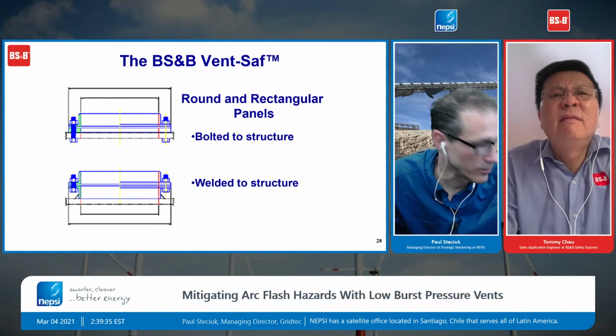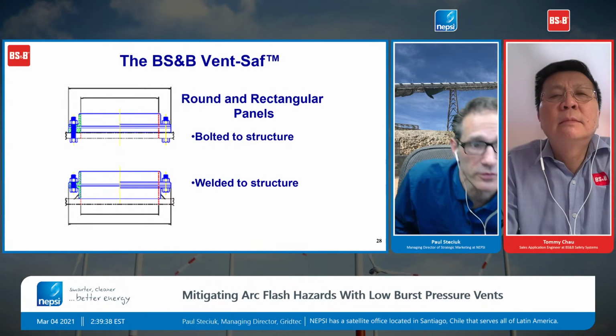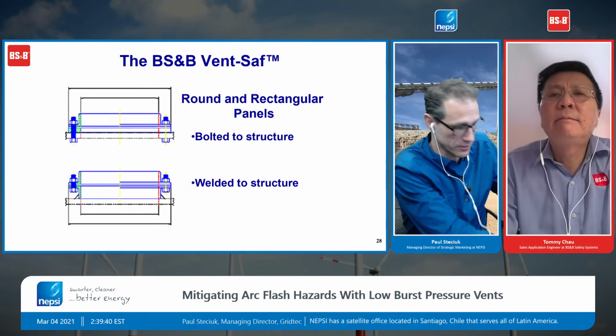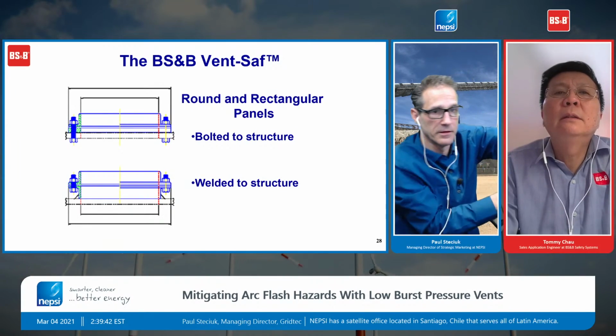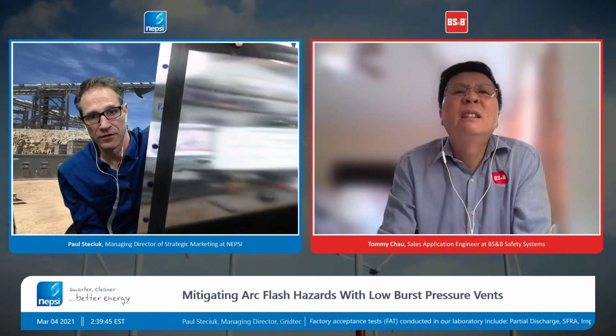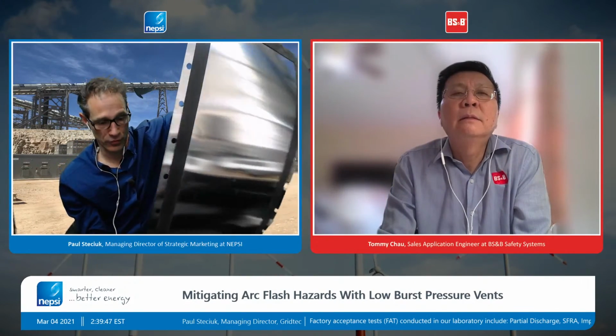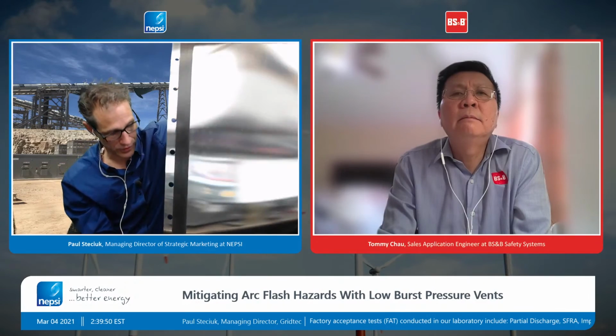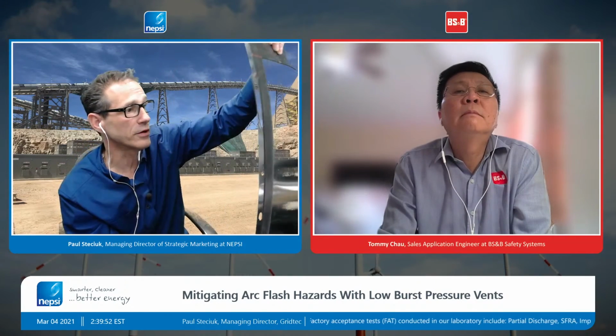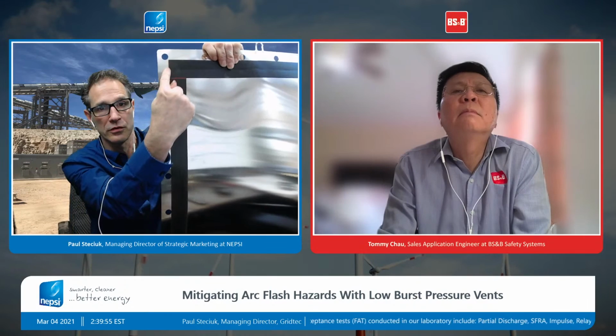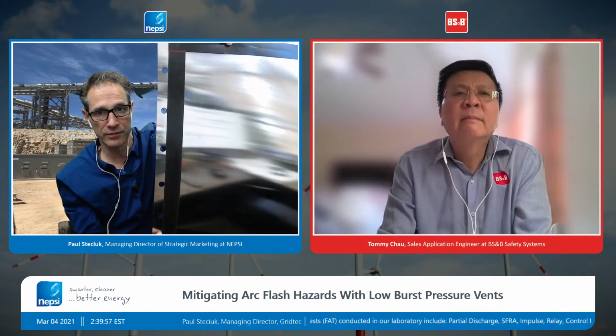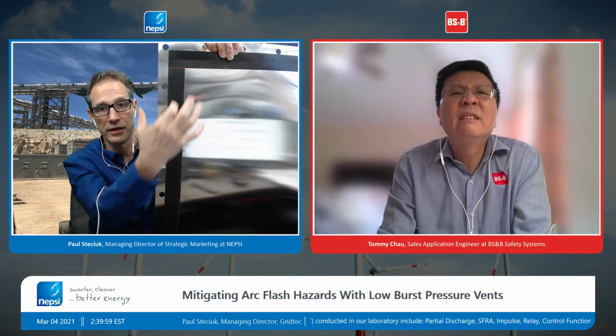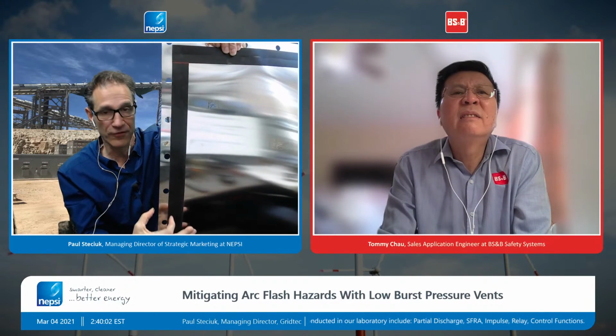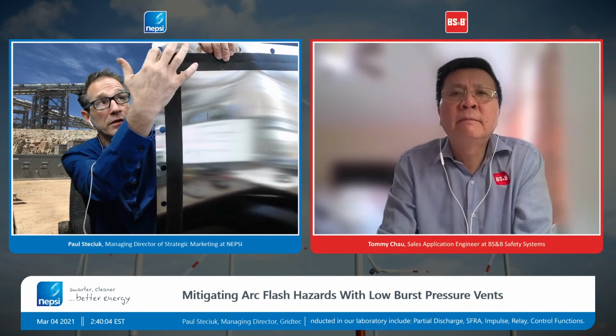So incidentally, I'll go back to what we do here, just so the audience knows. It's a very thin piece of stainless steel, more or less is what it is. I'm sure it's got more complexity than that because it's calibrated. But you can see we have holes along the whole perimeter of this burst vent, and we create an angle iron frame, and then we use basically half-inch bolts along the whole perimeter of this sheet. Yeah, and that's how we're doing it.